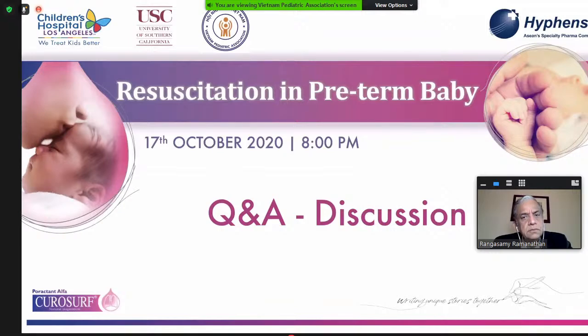The next question is, what is the recommended initial setting for volume guarantee mode? For example, what is the tidal volume, TI, and PEEP? Okay, so the tidal volume is 4.5 to 5 ml per kilo is the recommendation. Inspiratory time, 0.4 seconds. Rate, 30. And peak inspiratory pressure, you limit it to 30. Ventilators should be able to deliver 4.5 to 5 ml per kilo tidal volume using much lower PIP.